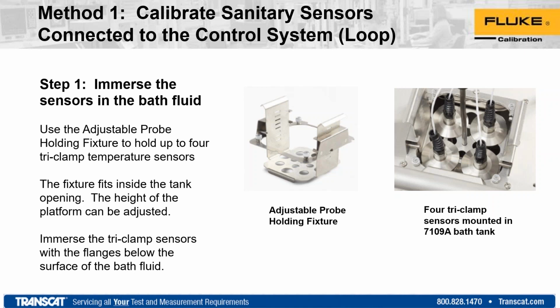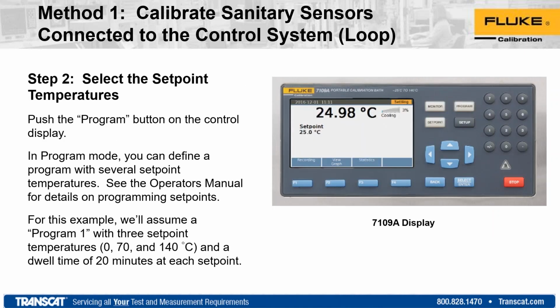Also, in the slides previously, we showed how some of these sensors are very short, 3-4 inches on the stem length, maybe even shorter. The probe holding fixture allows you to seat them down further from the top of the bath and hold them in the fluid. This can help with getting better immersion, because you do want to have the flange right at the fluid level to help reduce any stem conduction or errors contributed by ambient conditions. So this is showing a very basic physical setup, and then we'll keep talking through it.